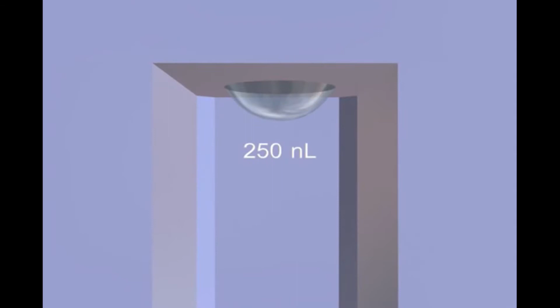Acoustic droplet ejection, or ADE, uses sound energy to move ultra-low volume droplets of liquid from a source location to an inverted destination with extremely high precision and accuracy. Echo systems move droplets of 2.5 nanoliters per ejection. To transfer larger volumes of liquid, multiple droplets are ejected from the source at up to 500 times per second.